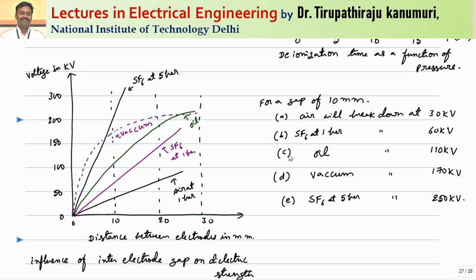Now let us see how by changing the distance between electrodes the dielectric strength changes, and how much gap is required to achieve the required dielectric strength or to break a given voltage. If air is kept at one bar of pressure — normal conditions — as the electrode distance increases linearly, the dielectric strength increases. For example, for an air gap of 10 mm, air will break at a voltage of 30 kV under normal conditions.